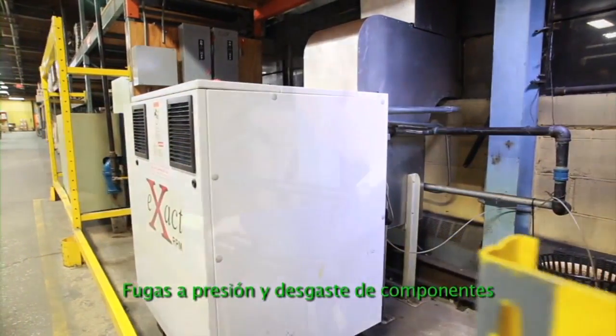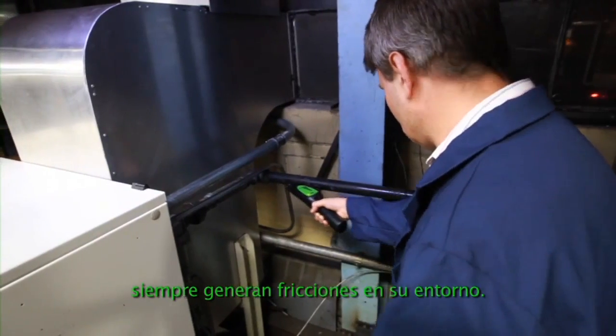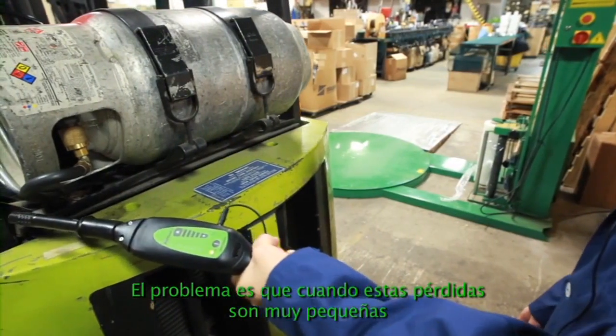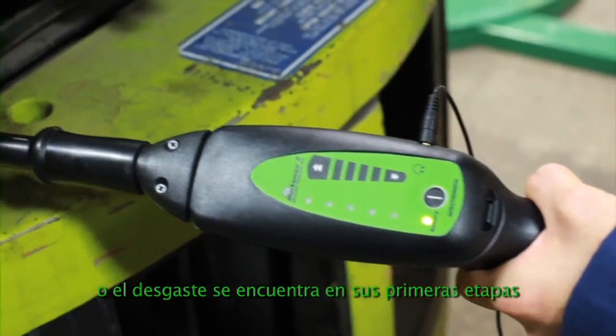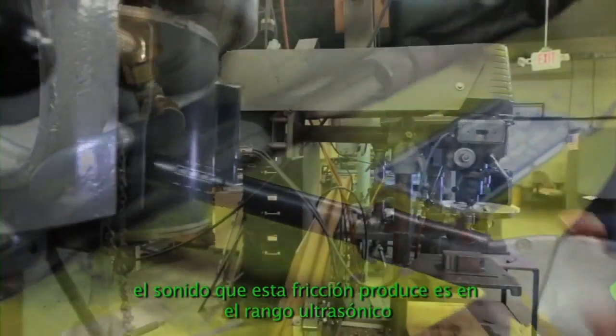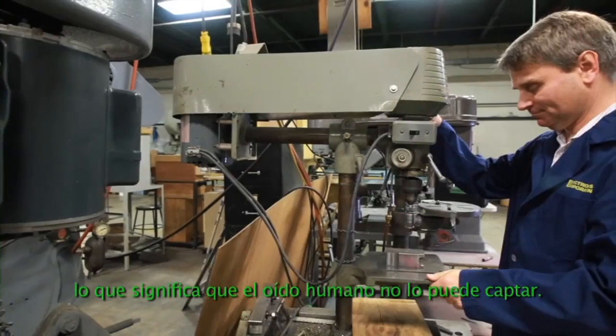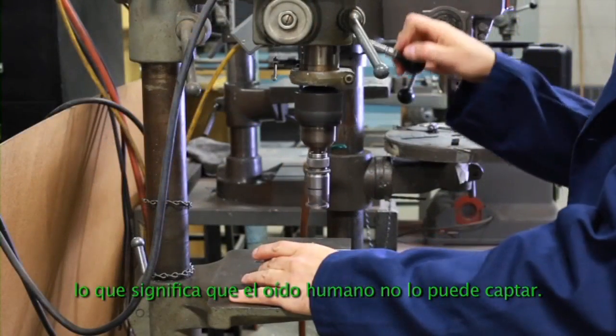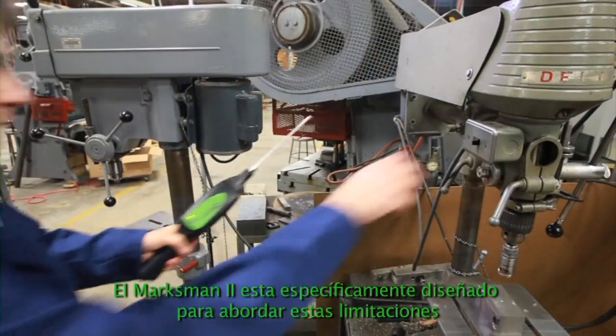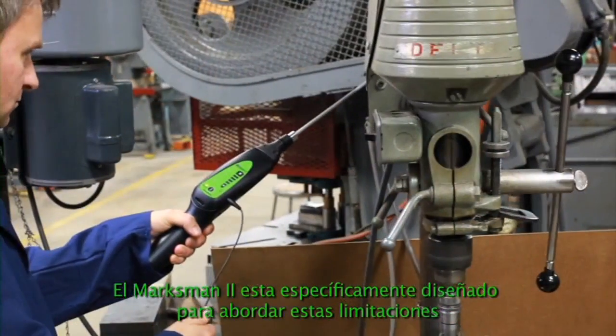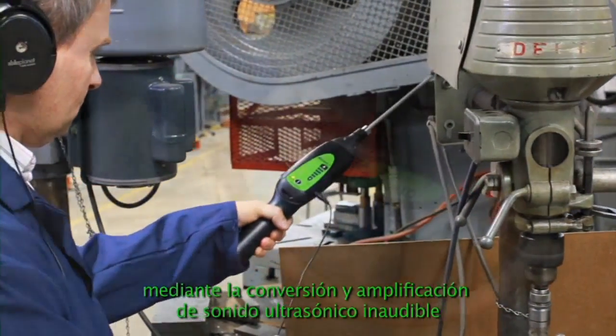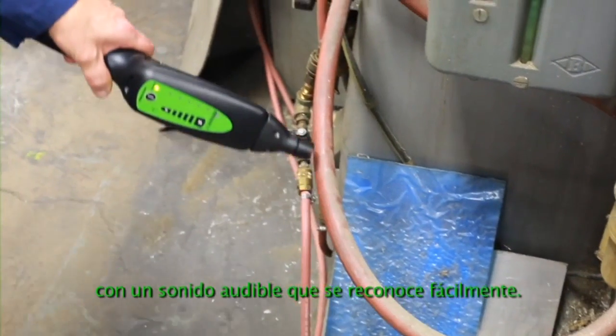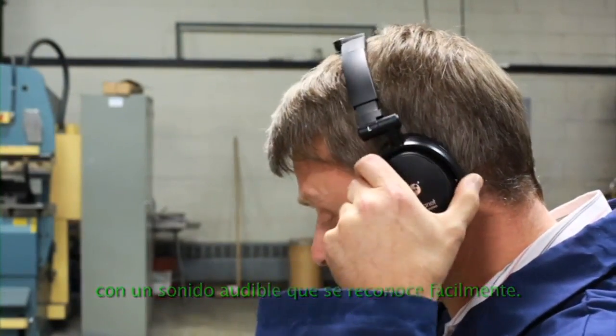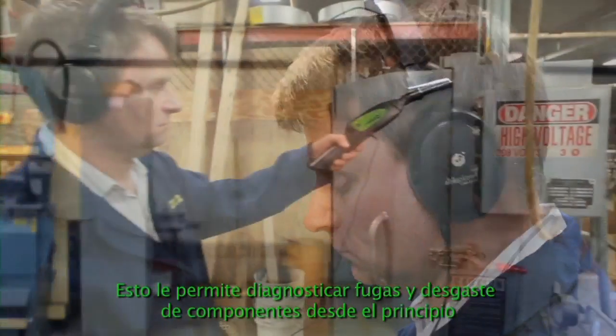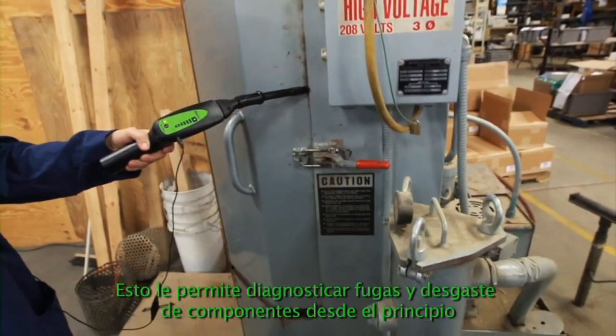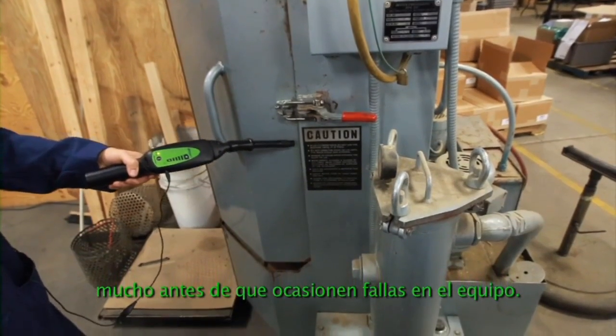Pressurized leaks and component wear always generate friction in their surroundings. The problem is, when these leaks are very small or the wear is in its early stages, the sound this friction produces is in the ultrasonic range, which means the human ear can't pick it up. The Marksman II is specially designed to address this limitation by converting and amplifying inaudible ultrasonic sound into an audible sound that's easily recognized. This enables you to diagnose leaks and component wear early on, long before they lead to equipment breakdown.